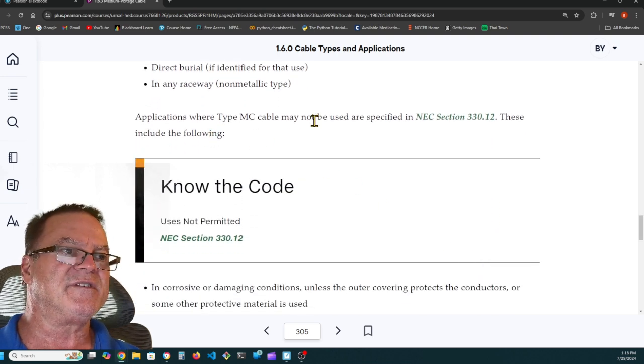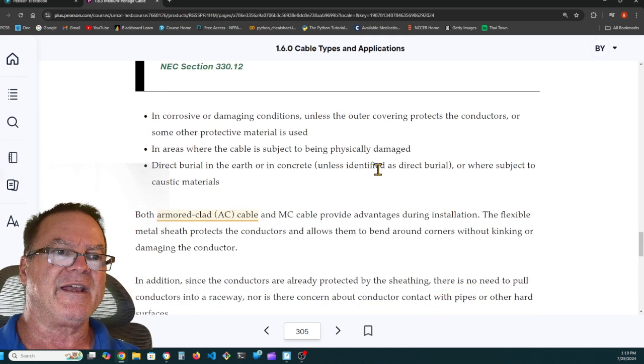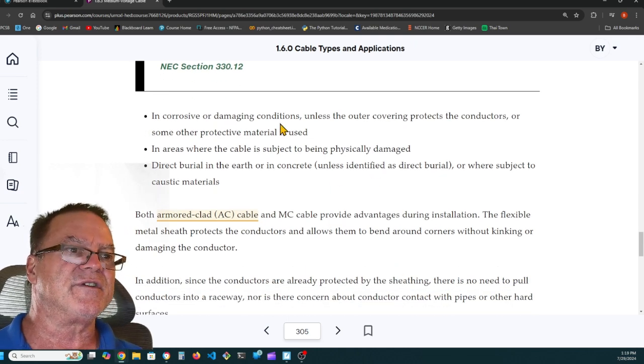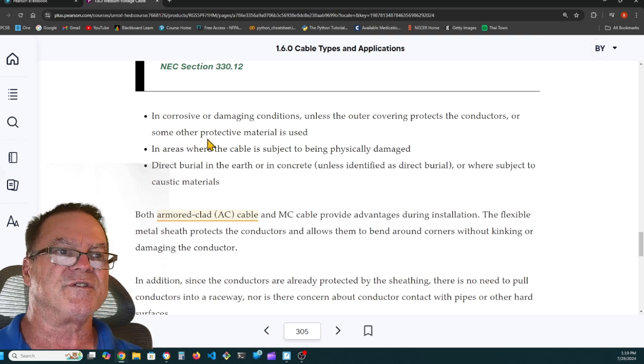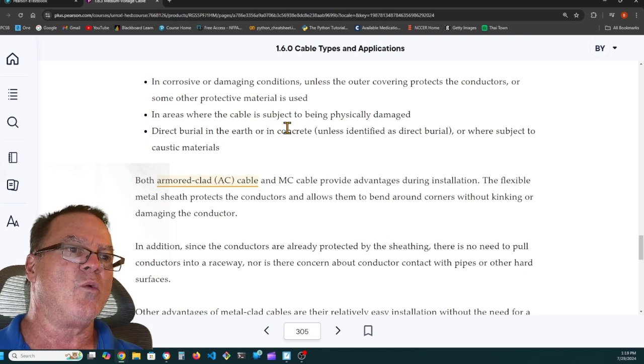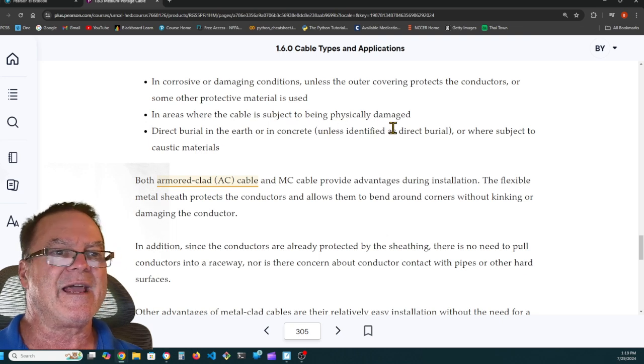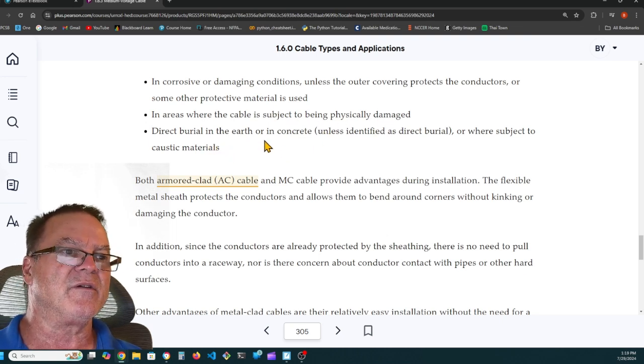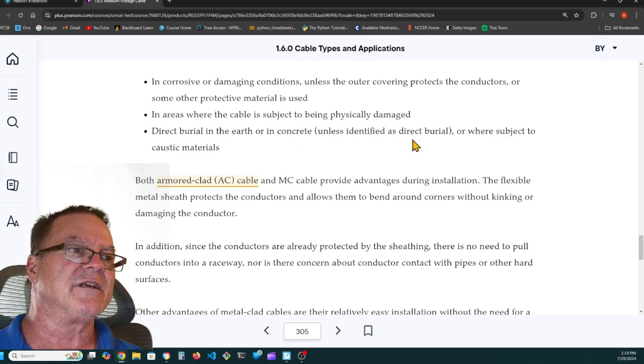Applications where type MC cable cannot be used are specified in section 330.12. These include the following: it cannot be used in corrosive or damaging conditions unless the outer covering protects the conductors or some other protective material is used. Cannot be used in areas where the cable is subject to being physically damaged. Cannot be used in direct burial with the earth or in concrete unless it's identified as direct burial or where subject to caustic materials.